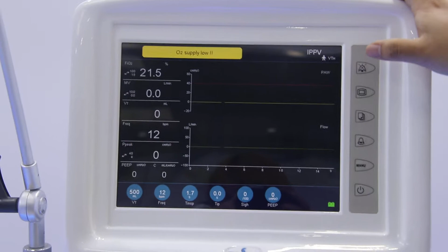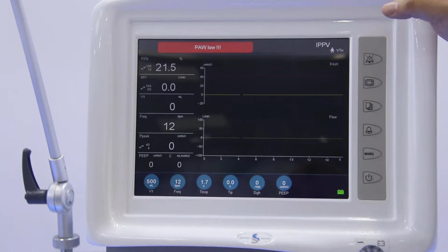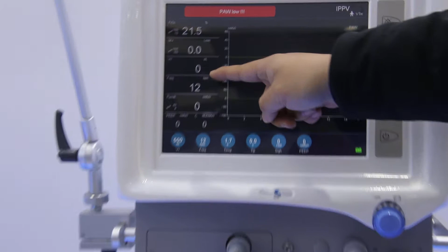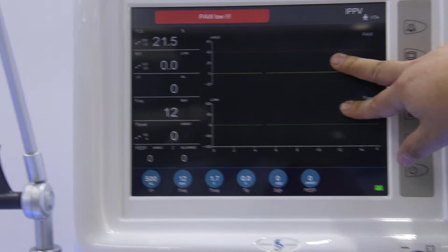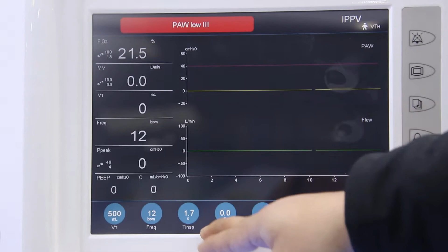On the main interface, we have a total of 4 parts. On the upper side is the alarming area, and the alarming area is separated into 2 colors, the red one and the yellow one. And for the voice frequency, we have a total of 3 kinds. You can hear them, and the most urgent frequency will be the first level that you need to solve, also with the red color. And here is the ventilation mode we are choosing now. On the left side is for the monitoring parameters, and on the right side we have 2 waveforms shown synchronously on the screen, and for each one of them you can choose the loop. On the lower side is the adjusting area.